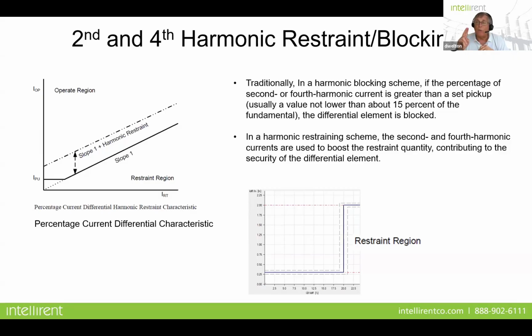Now, we use these words restraint and blocking, kind of like the same thing, but it really isn't, because if you're blocking the element totally, what's going to happen is that if you close in or energize a transformer and there's already a fault that exists, you're going to create an even bigger problem because you're energizing a transformer that's got a fault in it. Okay, so restraint means we're just going to move the restraint slope up higher and desensitize it if we see a certain amount of second and fourth harmonic in that initial waveform.